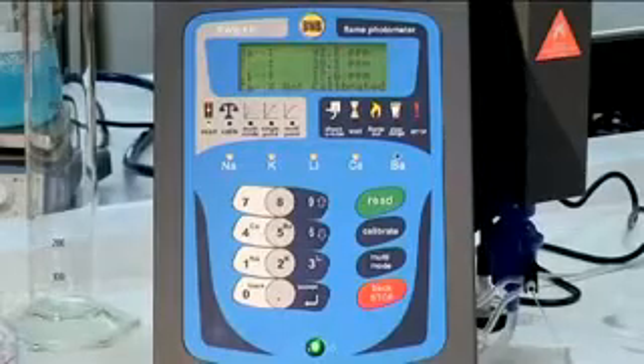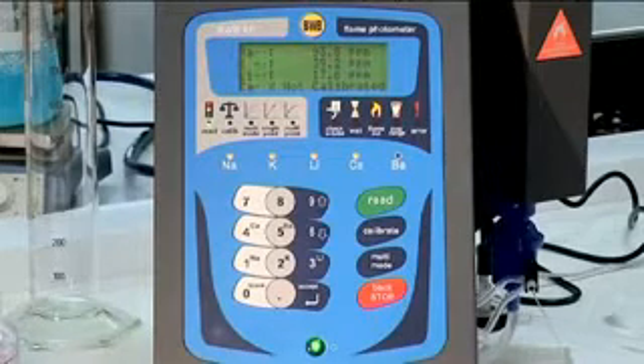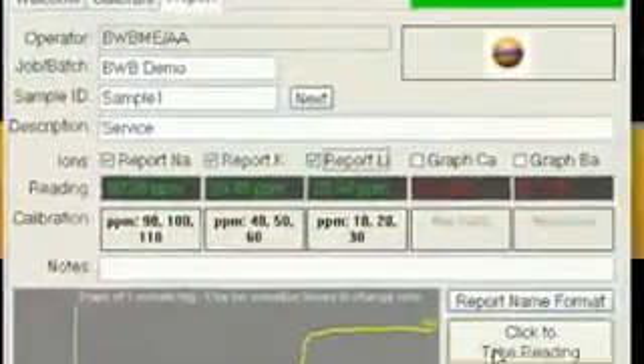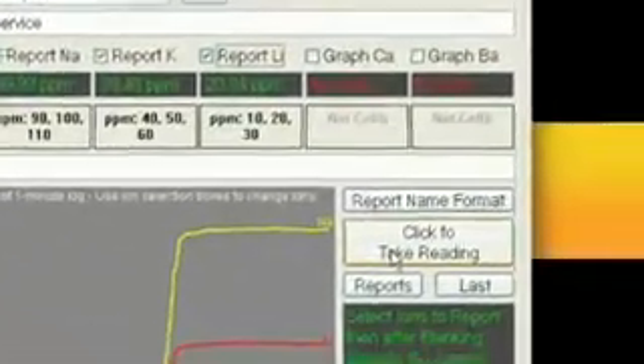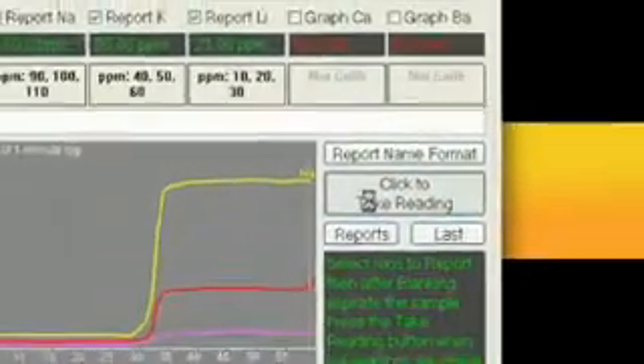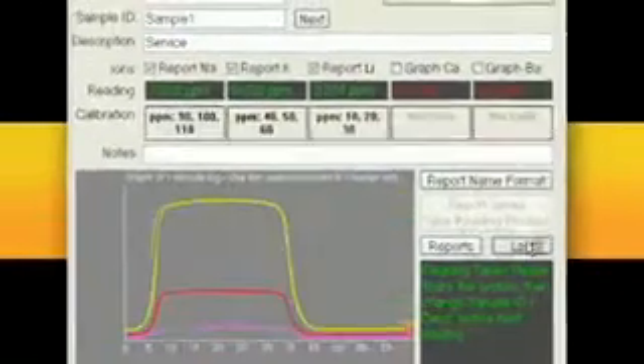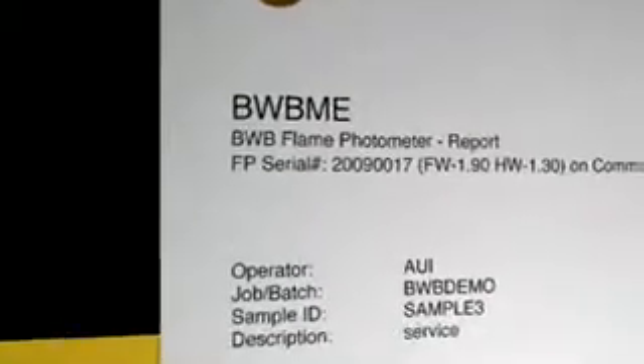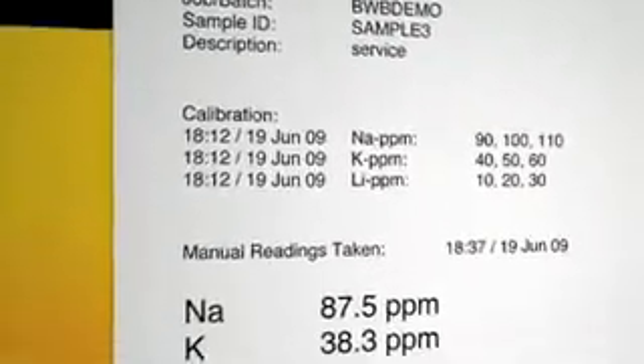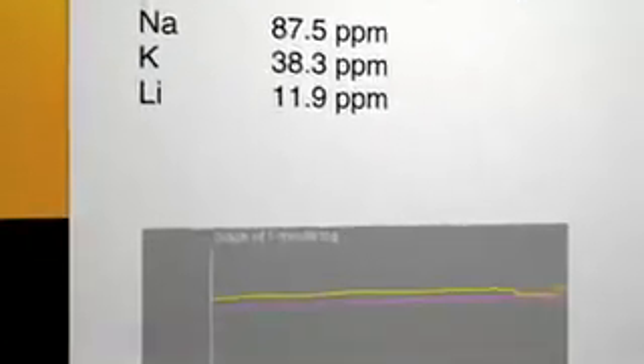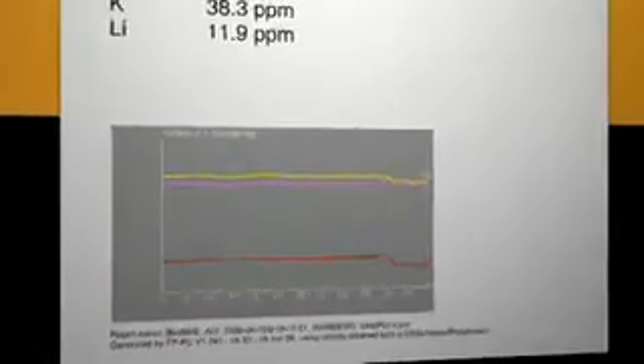Click on the Format button to open these preferences. You have a variety of settings available to you during setup which allow you to further customize your XP experience, including report names and report layouts. Close the box. Tick the ion box to watch it on the 1-minute graph. Any or all of the ions can be graphed as long as they are calibrated. The 1-minute graph is continually updated so you can monitor the instrument and see when stability is achieved.